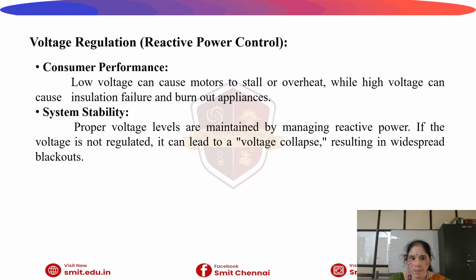The next topic is voltage regulation, which is basically reactive power control. For the consumer, low voltage can cause motors to stall or overheat, while high voltage can cause insulation failures and burn out the appliances. Therefore, system stability is to be focused on. Voltage levels are maintained by managing the reactive power. If the voltage is not regulated, it can lead to voltage collapse, resulting in widespread blackouts.